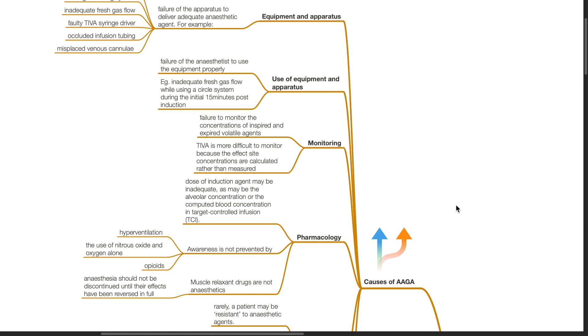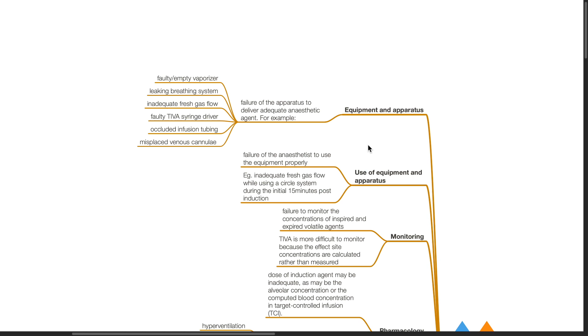Causes of AAGA. Equipment and apparatus. Failure of the apparatus to deliver adequate anesthetic agent, such as faulty or empty vaporizer, leaking breathing system, inadequate fresh gas flow, faulty TIVA syringe driver, occluded infusion tubing, misplaced venous cannula.